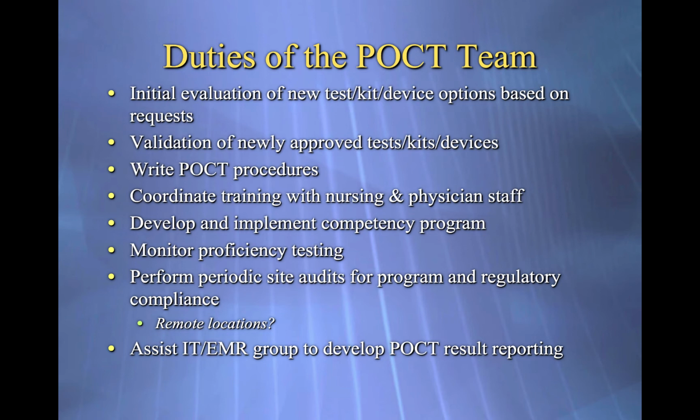Okay, duties of the point of care team then. Well, do initial evaluations of tests and kit devices based on new requests. Do validation of whatever is approved, write up point of care procedures, coordinate training with nursing and physician staff, develop and implement a competency program, monitor the proficiency testing, perform periodic site audits for program and regulatory compliance, and remove locations as necessary, take away their point of care.